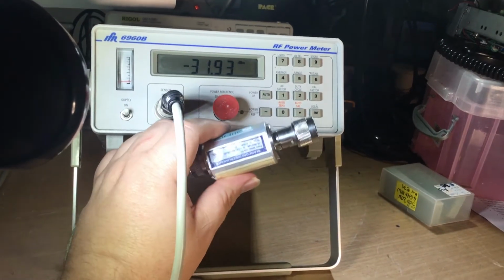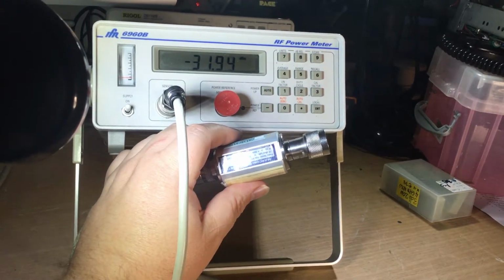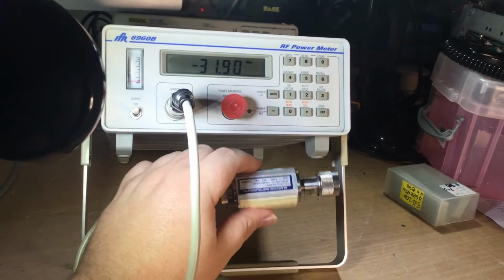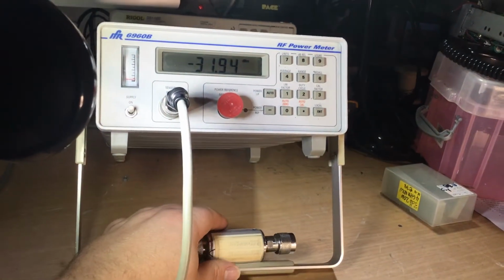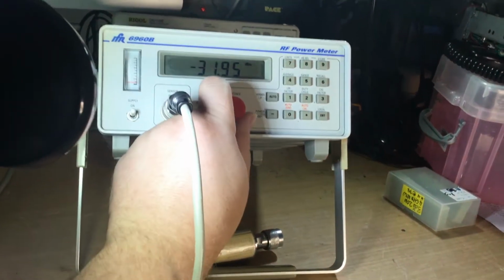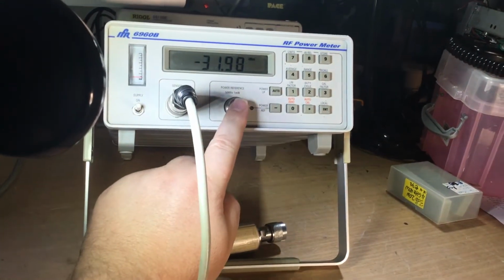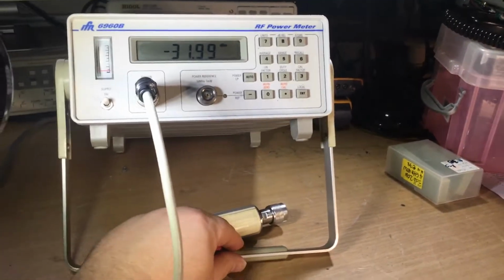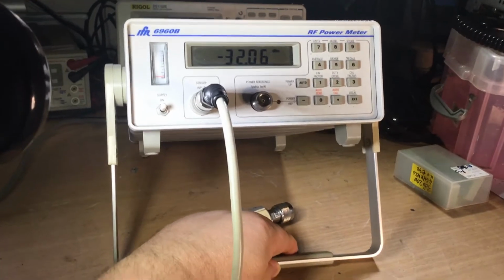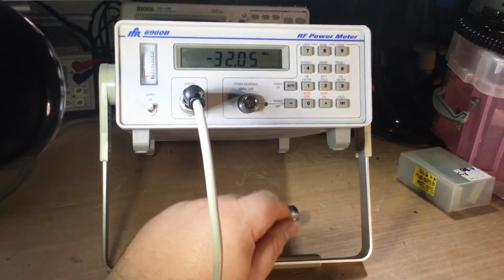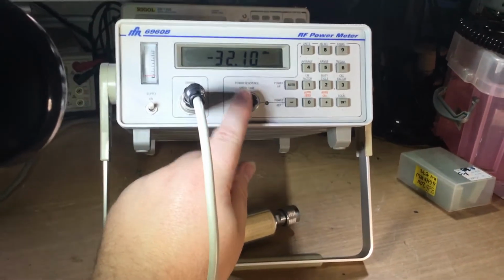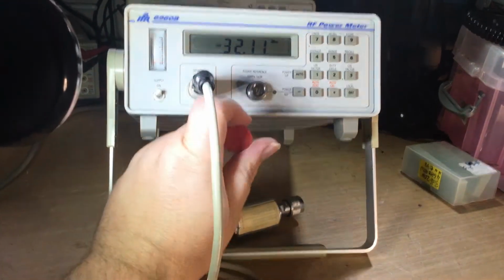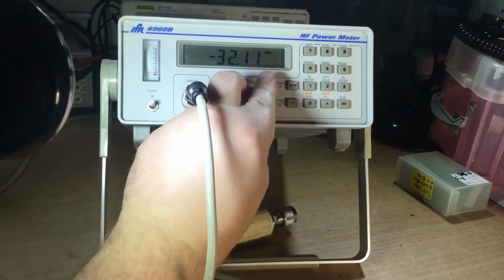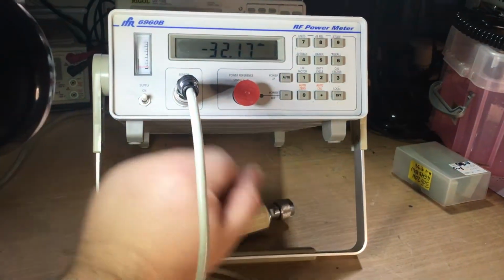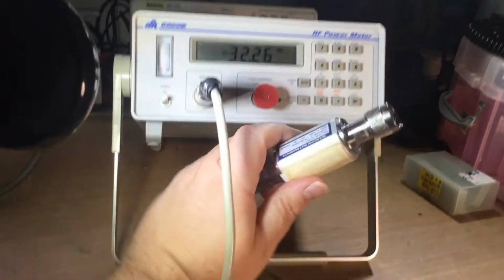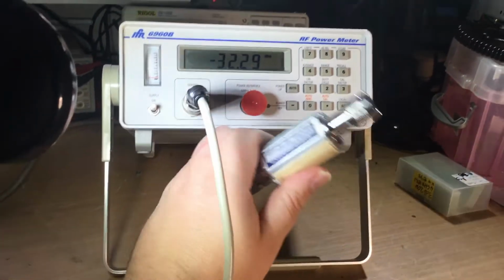Now you've got to be careful with these, because a lot of people assume because it's an RF power meter, they're often sold without the sensors, and then people assume that these N-type sockets on the front are actually where you connect your RF signal in, not realising that they can cause damage, because this is not an RF input, this is an output, which I'll go into in a moment. So be wary of that if you see these advertised and you're thinking of buying one, because often the sensors themselves cost far more than the instrument.